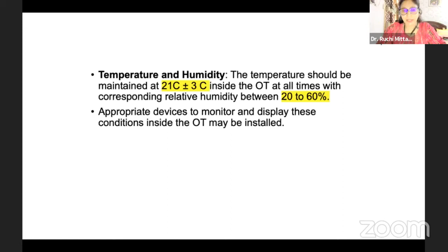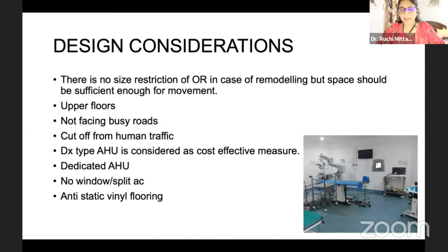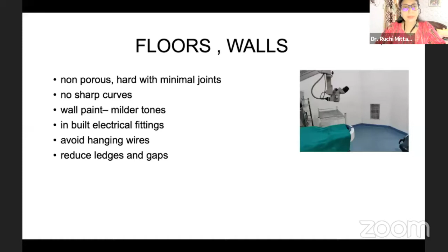The OT should be placed on the upper floors of the building. It should not face busy roads, and should be cut off from human traffic. A dedicated AHU should be there for one single OT, that means it should not be shared between two OTs. Window or split ACs are not recommended in the OR, and the flooring should preferably be anti-static vinyl flooring. The walls should be non-porous, hard, with minimal joints. There shouldn't be any sharp curves. Prefer to paint with milder tones, and inbuilt electrical fittings are recommended, that is, avoid hanging wires in the OR.